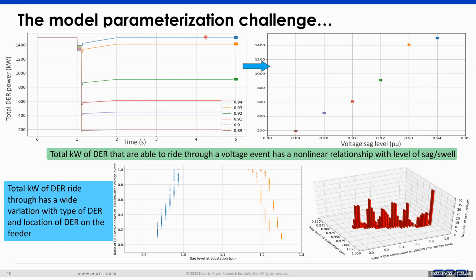So now if we take these endpoints, right? If we take this value of the active power that has remained after the fault has gone past, and if we just take these endpoints and plot them against the voltage level, we get a curve like this. So one can say that, okay, this is a reasonable enough linear trend. We can fit a linear line to this curve, and we can get our response, or our tripping behavior. But where it becomes complicated is that this kind of linear trend holds for this topology of DER.